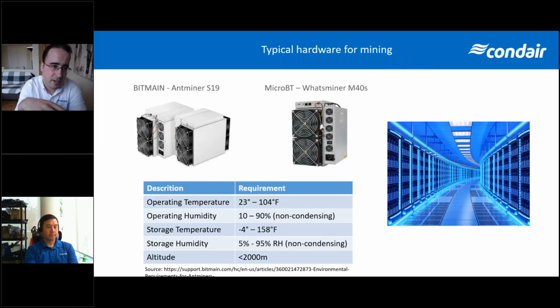One of the things you can see, for example, is some of the typical equipment for mining digital currencies. If you see the requirements, they are quite broad. They go from 10 to 90% RH, and 23 to 104. So they are typically not as critical as a colo center or hyperscale data center. You can have a big range, but still the temperature is 23 to 104, so you will need cooling, of course, because all these miner facilities have a huge heat load. So like I said, that's where we can help.